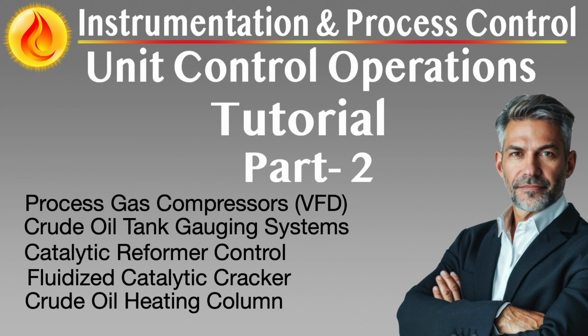emission targets. Catalyst management in continuous catalyst regeneration, CCR, reformers introduces unique automation needs. Catalyst circulation rate, coke burn profile, regeneration temperature, and reintroduction timing are all under advanced control. The system must balance deactivation in the reactor with regeneration capacity to maintain stable activity and selectivity. Smart algorithms assess catalyst aging, monitor pressure drop trends, and optimize regenerator conditions, ensuring long-term performance without frequent shutdowns.